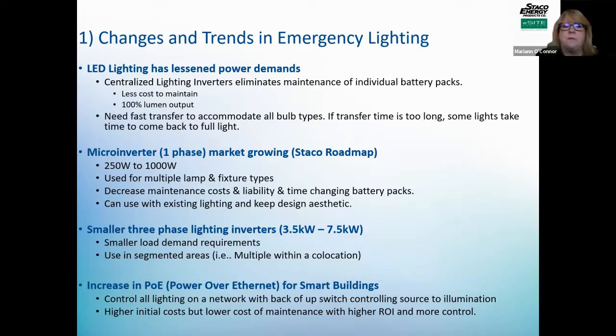And they can be used for multiple lamp and fixture types. And it decreases the cost on the maintenance, increases the efficiency and the time it takes to change out battery packs. And you can use these microinverters on all existing lighting. And what's nice too is depending on where it is, you can keep the design aesthetic. So that's very important. And again, because of these lower loads, we're either going with smaller units or the units are able to back up more lighting fixtures.